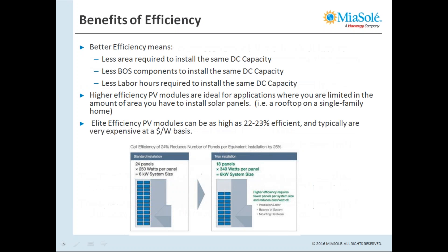Now that we understand efficiency, let's understand the implications. If you had the choice between a 23% efficient module and a 16% efficient module, which would you choose? On the surface, the 23% module looks very attractive, but better efficiency does not actually guarantee better performance. However, better efficiency does mean less area required for the same DC capacity, and less balance-of-system components to install the same DC capacity.